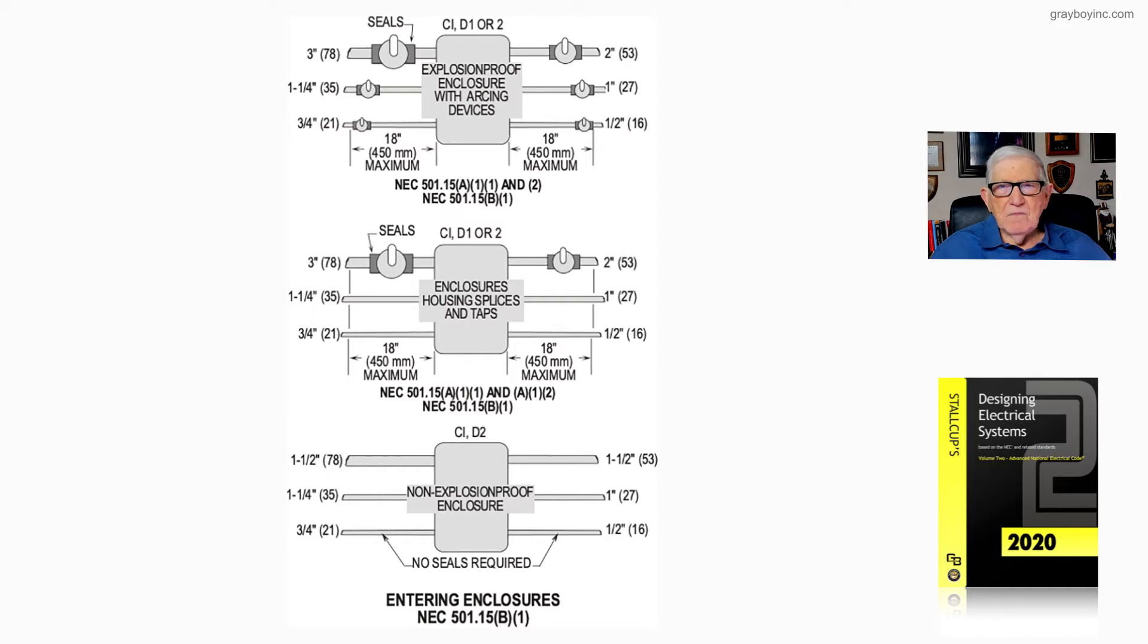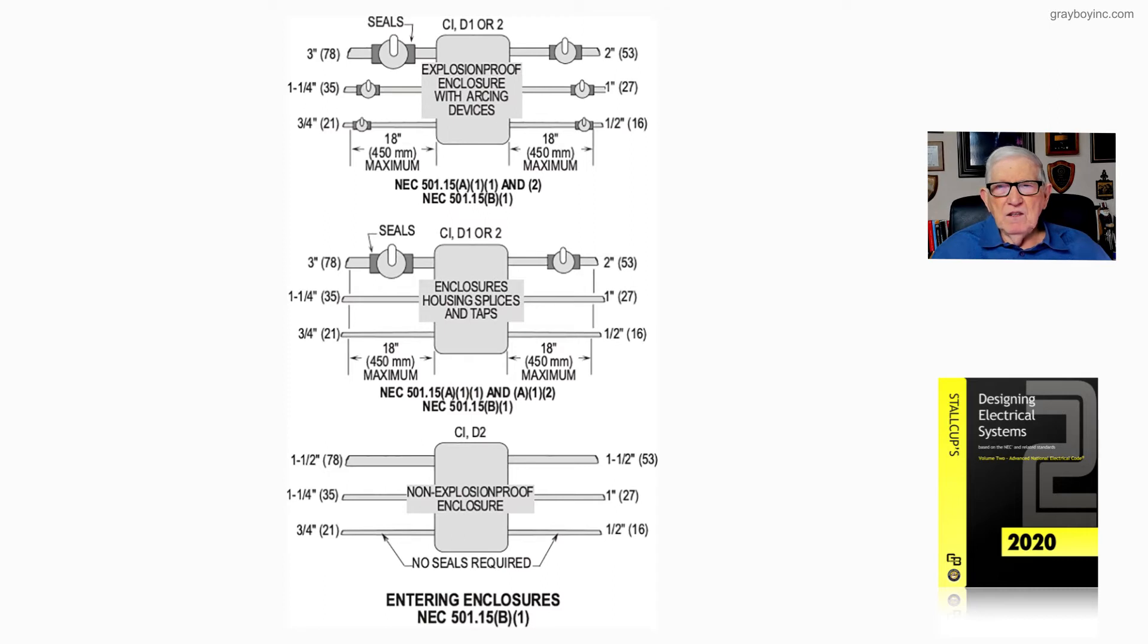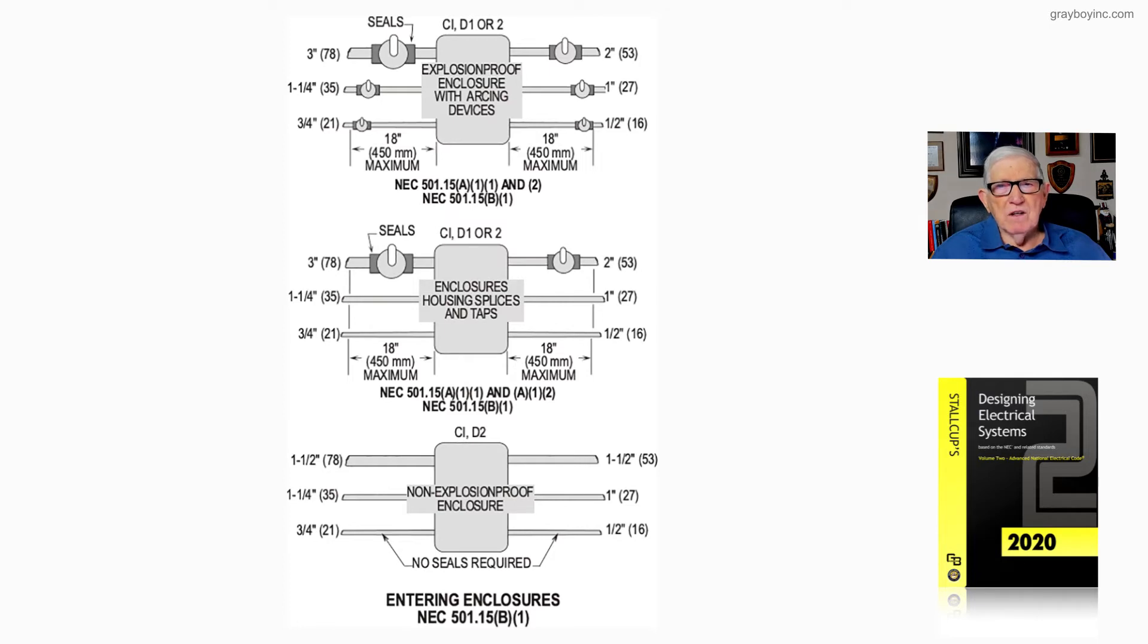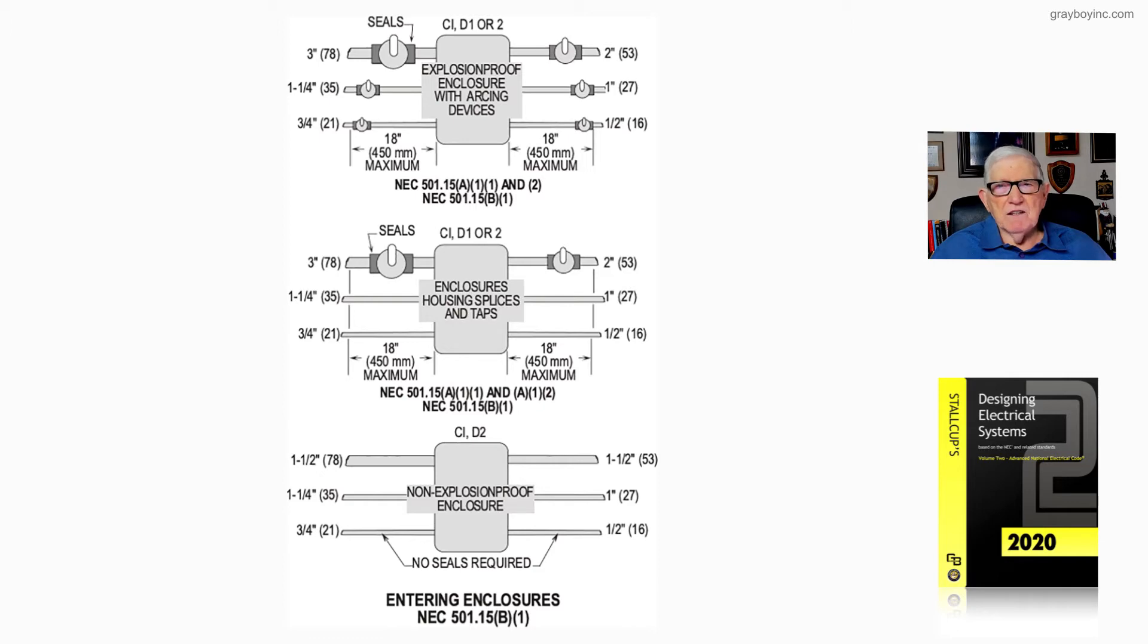The very top portion deals with explosion-proof enclosures with arcing devices. So we know we have arcing devices and all conduits have to be sealed within 18 inches of the enclosure if the enclosure is not self-sealed.